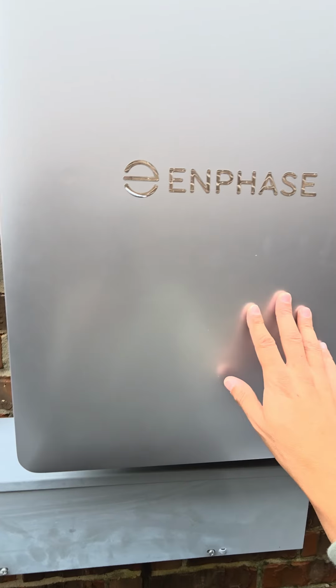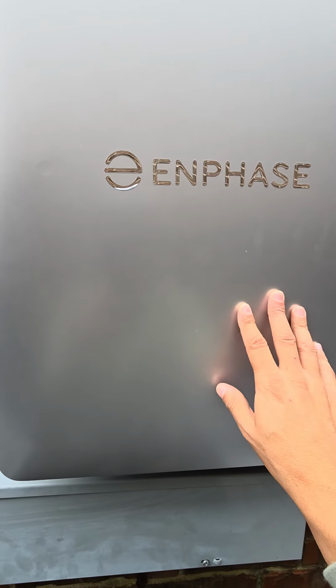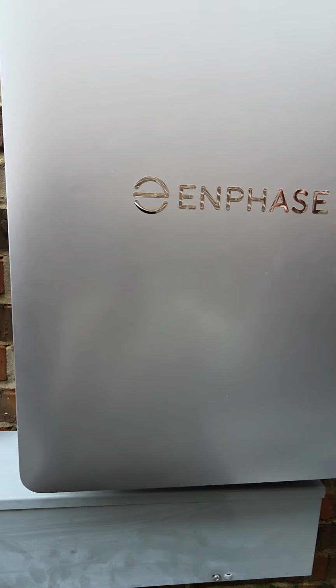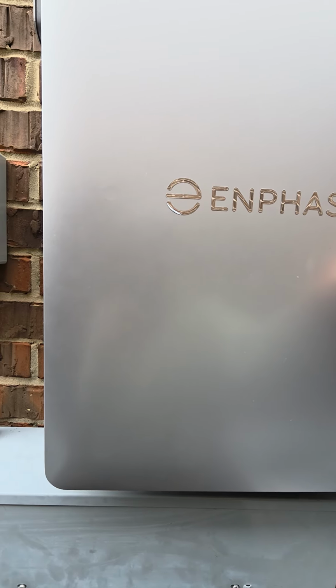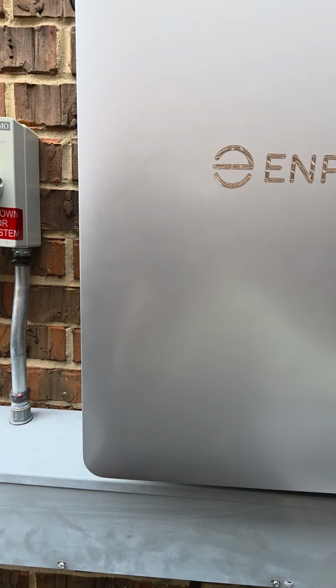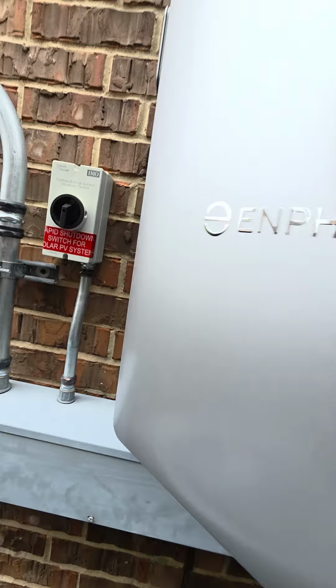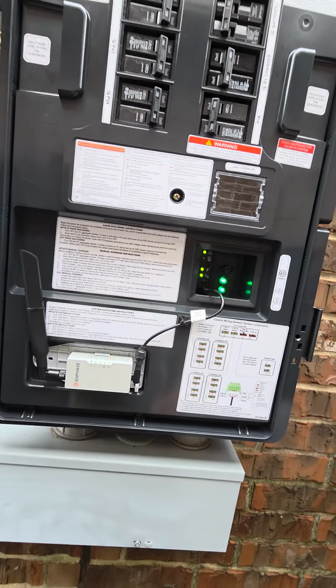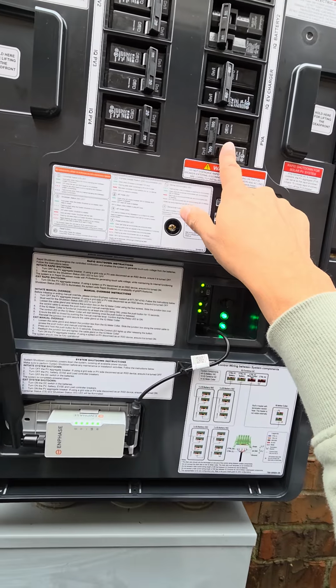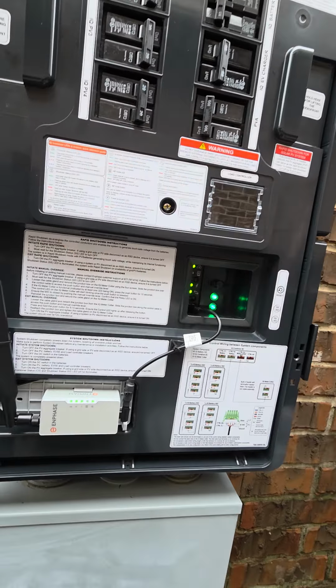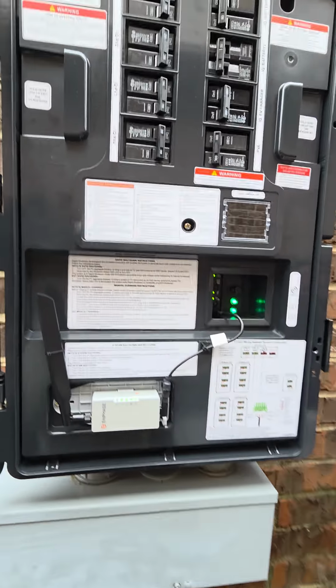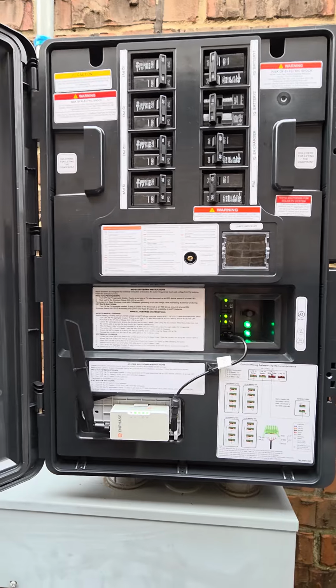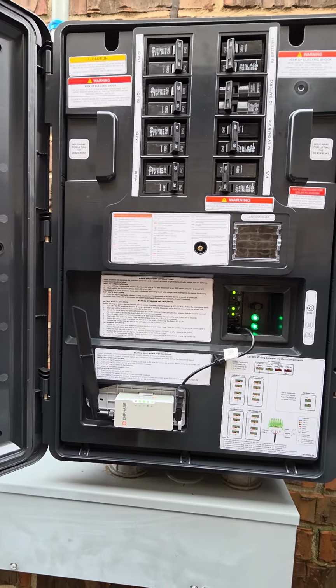The combiner does have the capability of doing storage solar shutdown from their PV breaker, but there were notes in there. The PV aggregate breaker, basically, if you just turn this off, it will shut down everything on the solar and battery side. But I was reading that some places require ease of access.